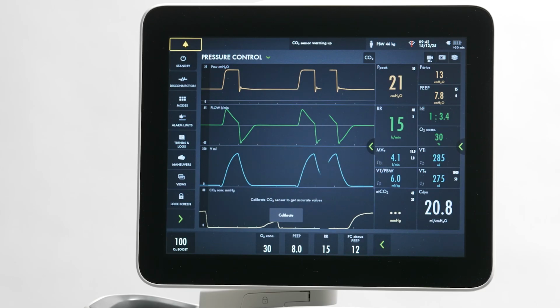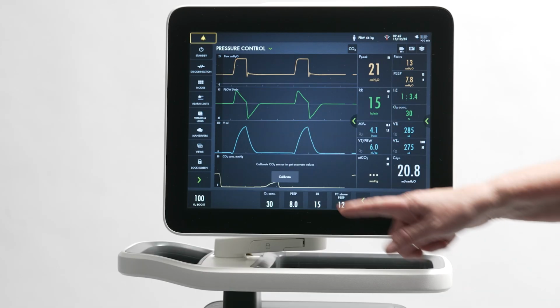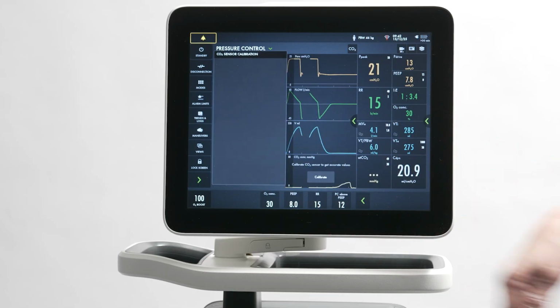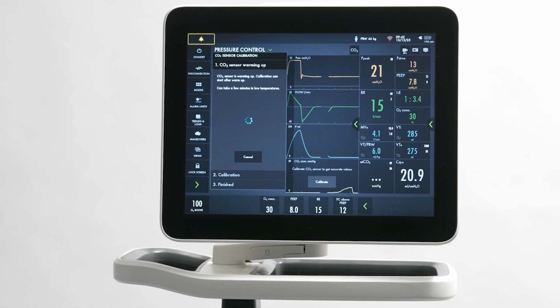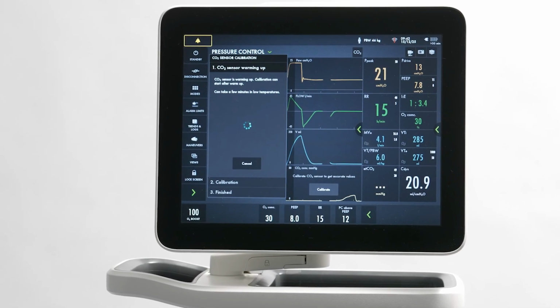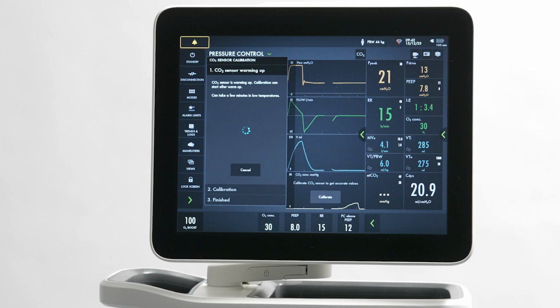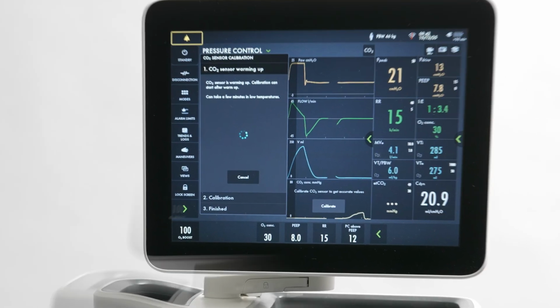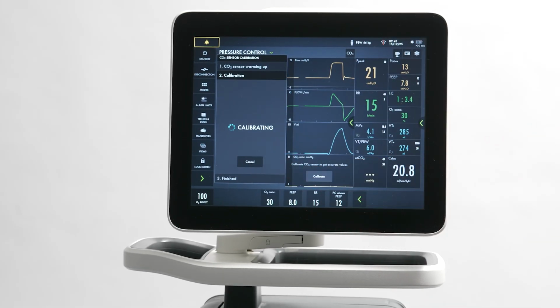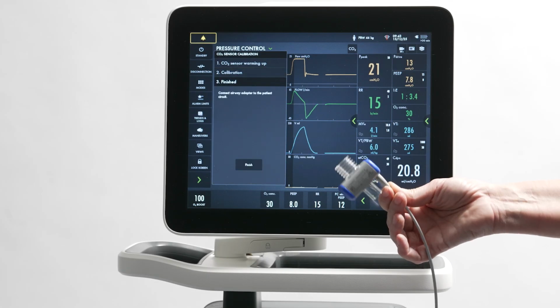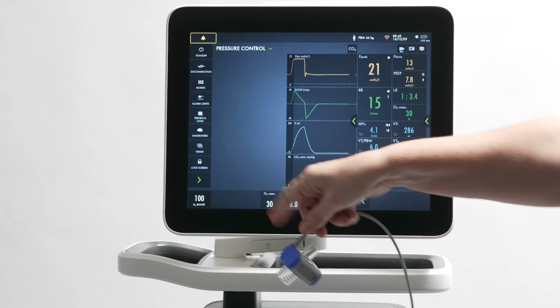I will now show how to calibrate the sensor. Each step of the calibration is displayed before beginning the calibration procedure. The sensor needs to be warmed. This is done automatically. Note this can take a few minutes. Final step is to connect the CO₂ adapter to the patient circuit.